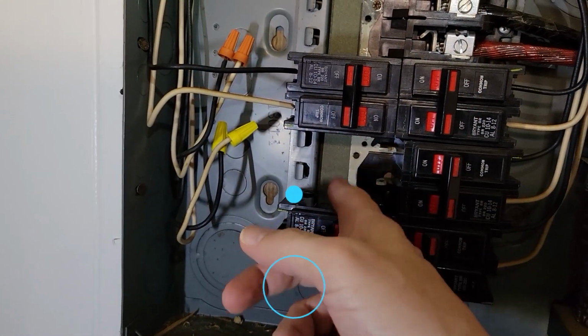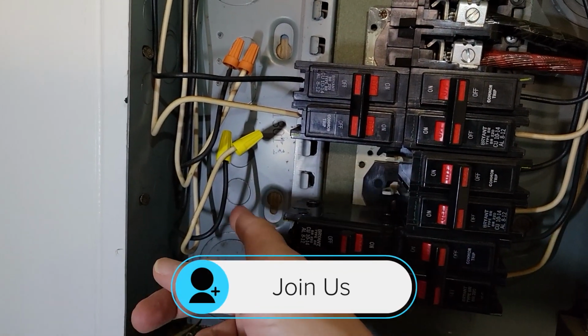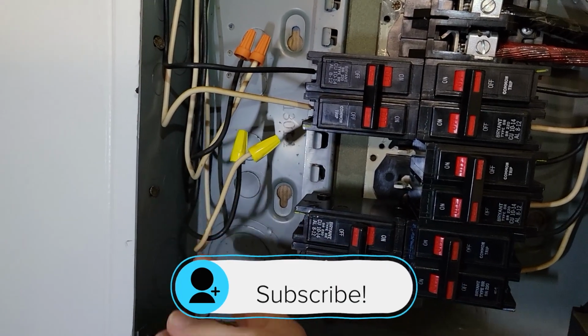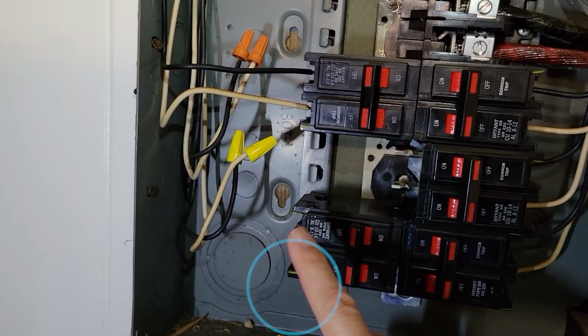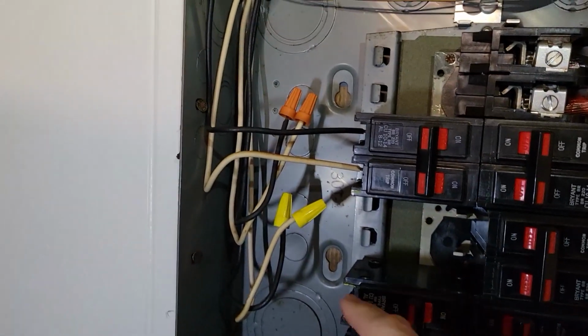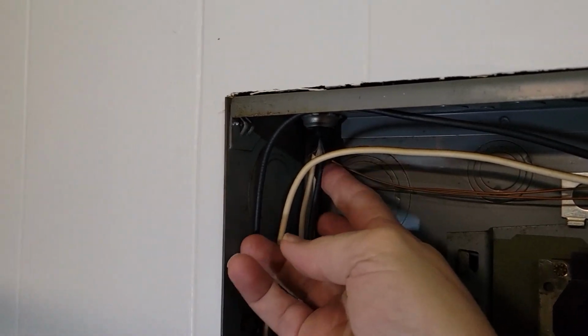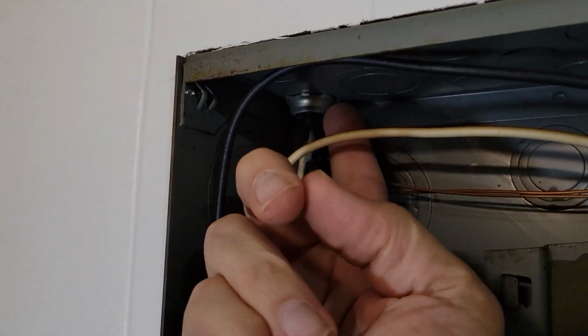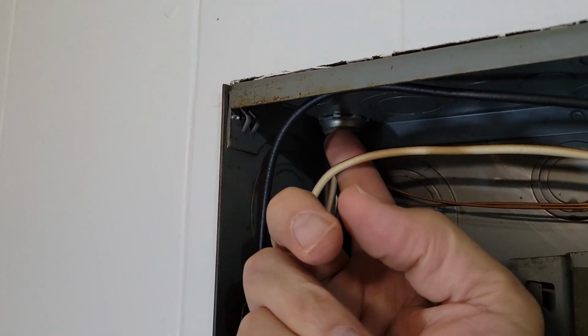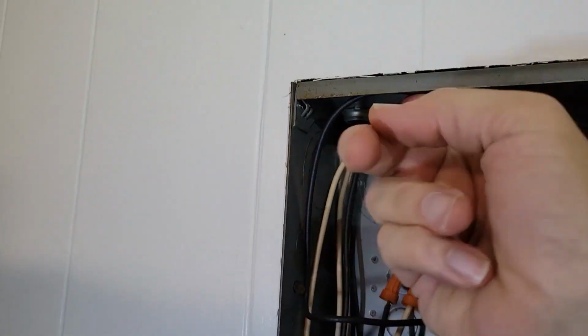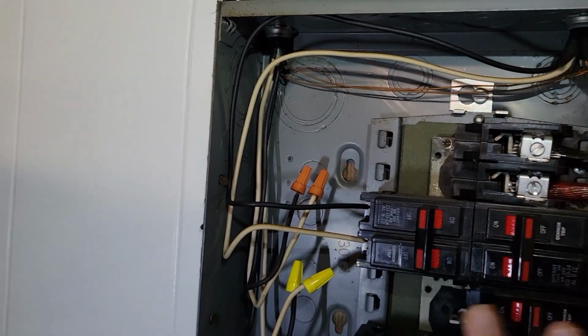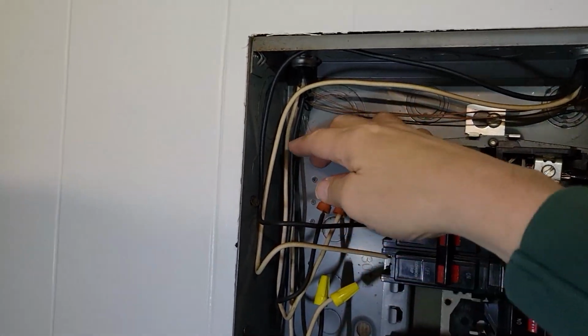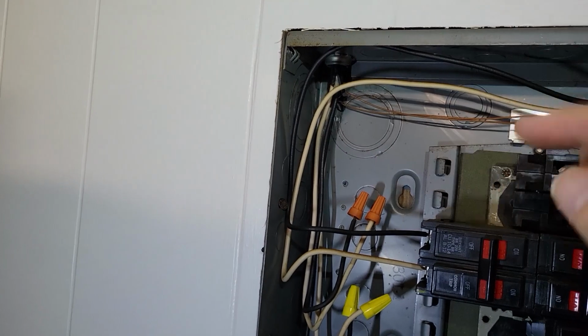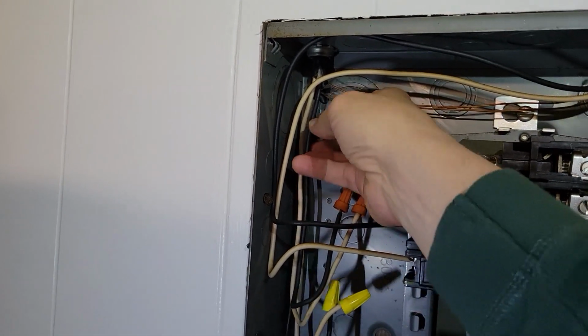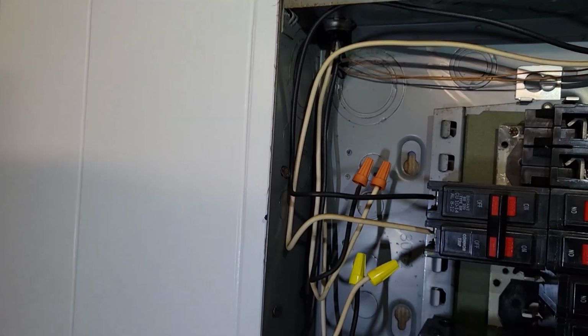At this point, I've taken out the old circuit breaker. I've disconnected the wires that belong to that particular circuit breaker and to the one below it, only because those two circuits actually go up into this feed point. So I'm just going to pull both of these out. Again, this is a totally dead thing here, so I can afford to lose these wires. They will basically pull the new wire up into the attic for me.